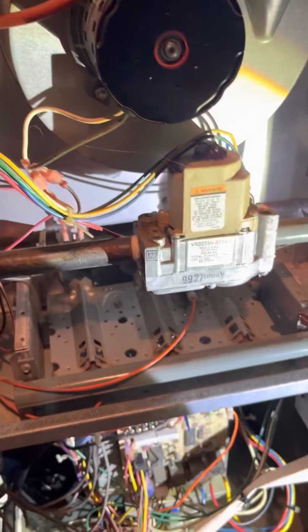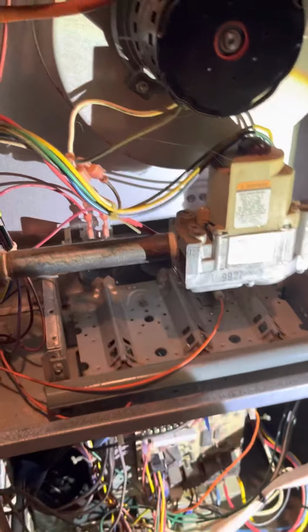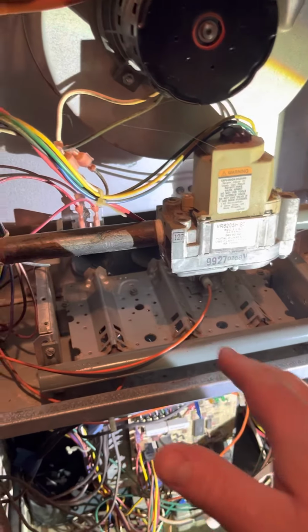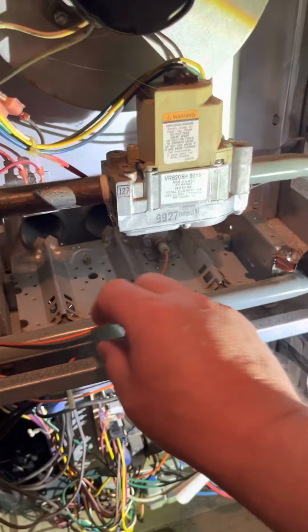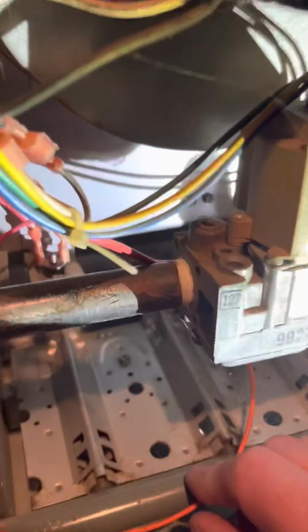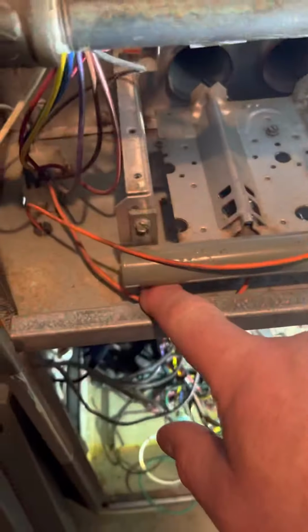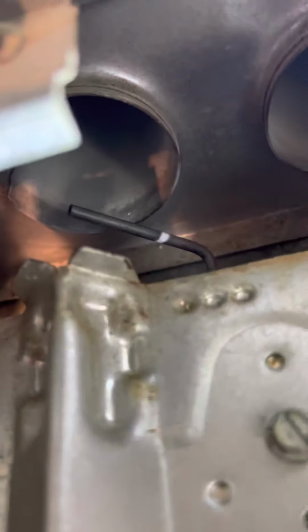I'm going to shut the gas valve off. So now we have a flame sense failure. The flame sense coming back on the orange wire here is going back to the board now. Here's my flame sensor in there. You see that rod, and that's what gets dirty. And you need to clean it.